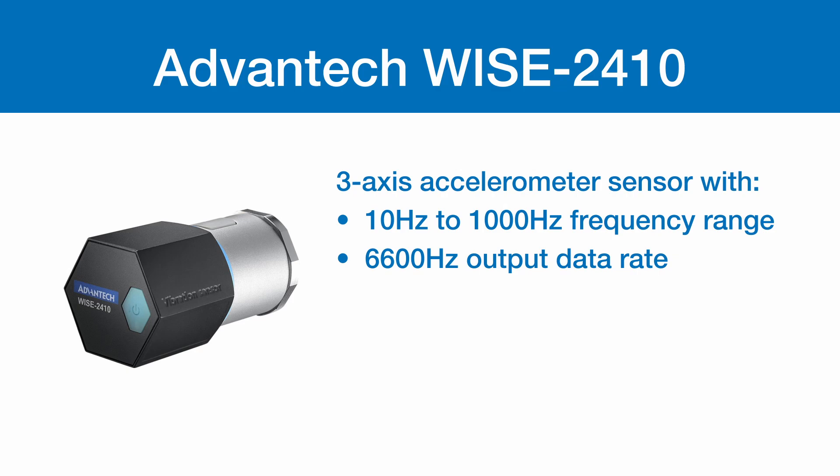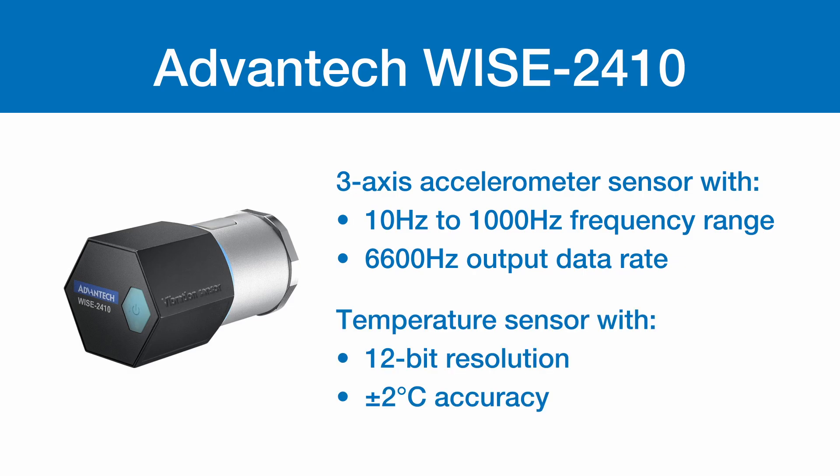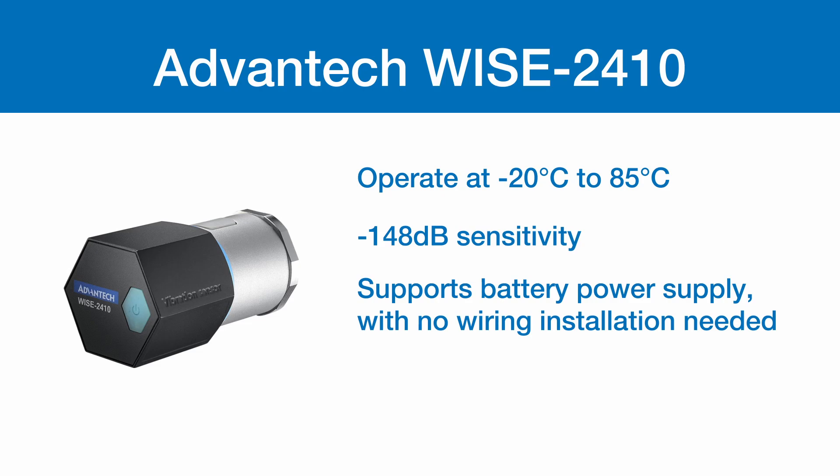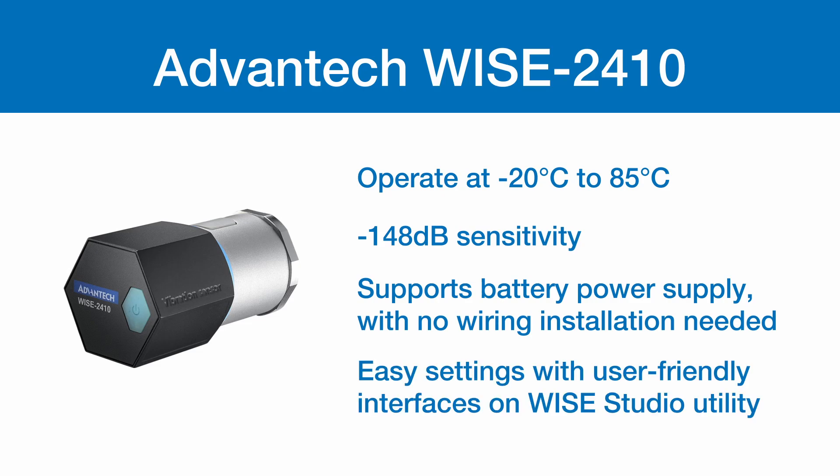The sensor has a 3-axis accelerometer with a 10 Hz to 1000 Hz frequency range, 6,600 Hz output data rate, and a temperature sensor with 12-bit resolution and plus or minus 2 degrees Celsius accuracy. The operating temperature is negative 20 to 85 degrees Celsius. It has a negative 148 decibel sensitivity, supports battery power supply with no wiring installation needed, and easy settings with a user-friendly interface on the WISE Studio utility.